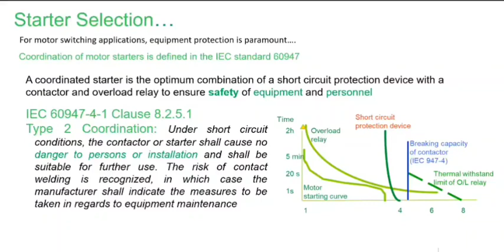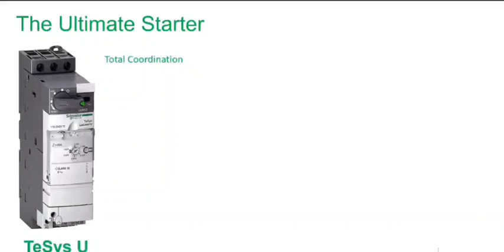This is where total coordination comes into picture, where if a particular short circuit fault comes for a particular level, then it can take up to three short circuit currents of the same level. So what happens, let's say a 50 kiloampere short circuit current, you have designed your MCC accordingly. After that 50 kiloampere short circuit current, your contactor will get welded, you may not be able to use the same components for the next fault. In that case, you will have to replace your existing component. Now in TeSys U, which is completely total coordination as per IEC standard, you can use the same starter for up to three short circuit faults.